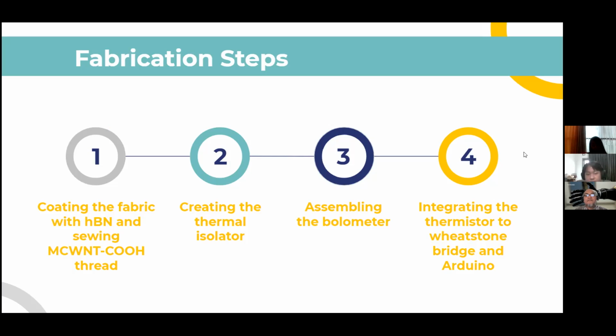The third step is to put together all the parts to make the bolometer. The inner and outer casing will be covered with aluminum foil, the HBN coated fabric is placed below the lens and glued between the openings of the casing, with wires attached. Both ends of the thread connect with the thermistor, the ZnSe lens is placed on the inlet of the casing, and a straw is attached for the vacuum.